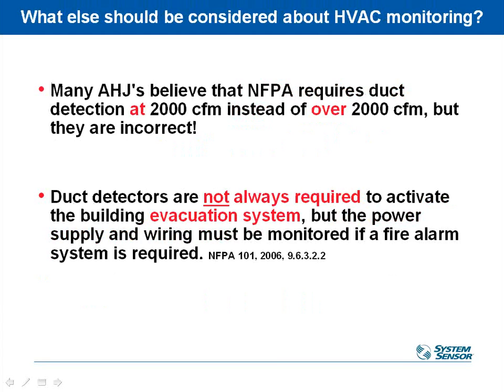Some authorities having jurisdiction have the false belief that NFPA requires a duct smoke detector for systems that are 2,000 CFM. That's not true. It has to be over 2,000 CFM. I realize it's only a 1 CFM distinction there, but a lot of air handlers are listed on schedules at 2,000 CFM. It's a very common size, obviously, 5-ton unit.